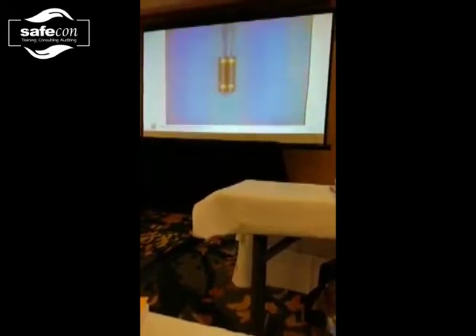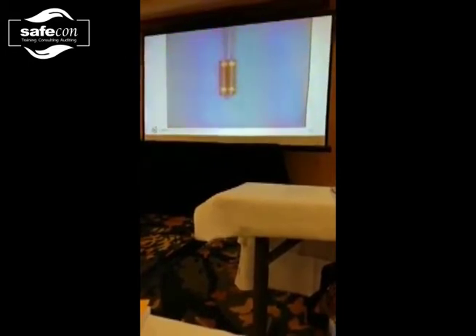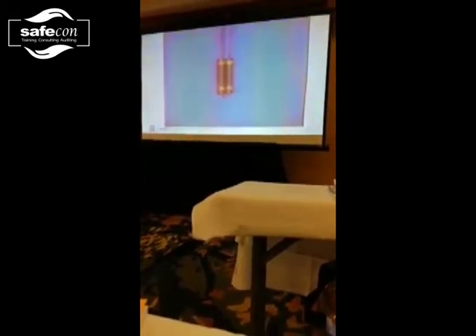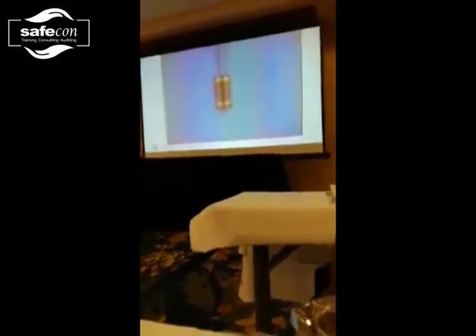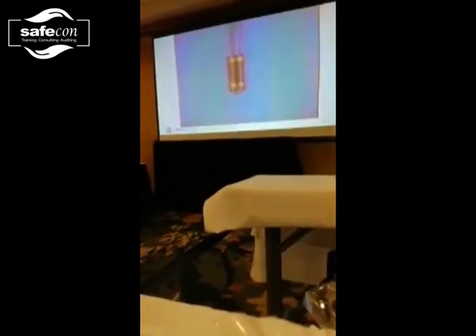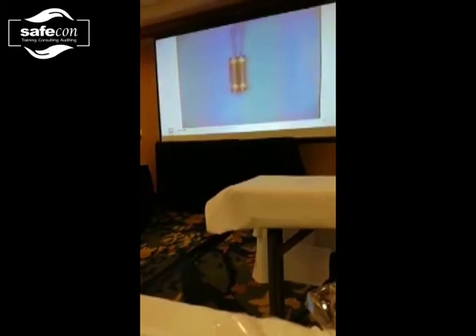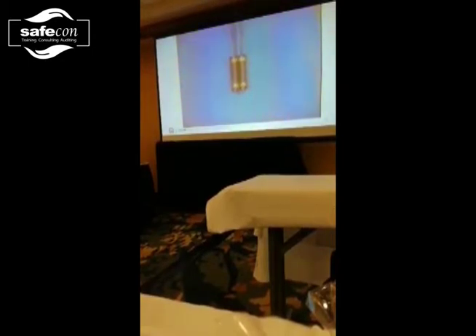So I do some training for Toyota manufacturing in the United States. I haven't been to Japan for them yet, but anyway, a friend of mine that I work with there calls it a coming out party. When we install equipment that is rated less from a short circuit current standpoint, when the available fault current is greater than the short circuit current rating of the equipment, as engineers, you all well know that the equipment can come apart. It won't sustain under a fault condition, it'll come apart. He calls that a coming out party, where all the pieces and parts come out the grate. It's not what we're trying to do. So you'll see that in these applications.